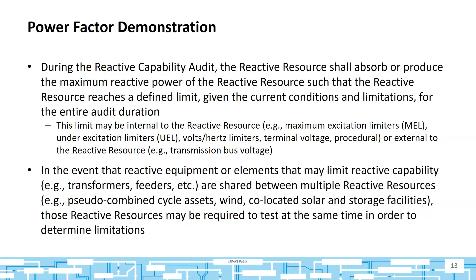And where there are multiple devices, say connected on a feeder, or where there's a power controller controlling multiple devices, we will run this test running all of those devices that may interact with each other at the same time to make sure there isn't any common limitation or anything like that. And the result of this test will be a megavar capability, lagging and leading, that will be associated with the resource going forward. So next slide.